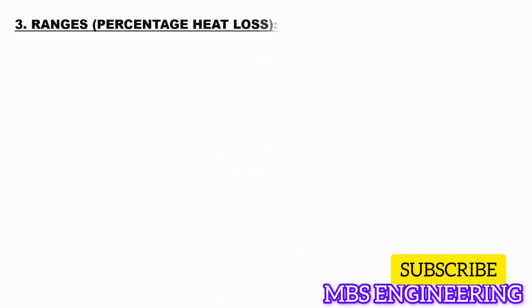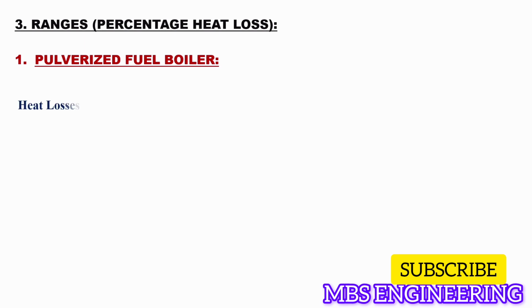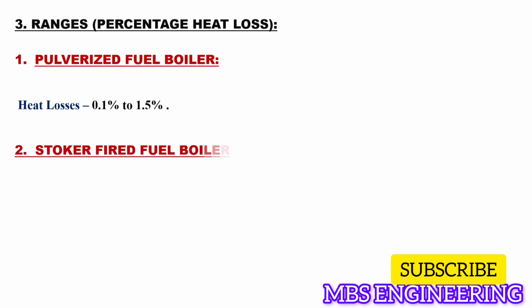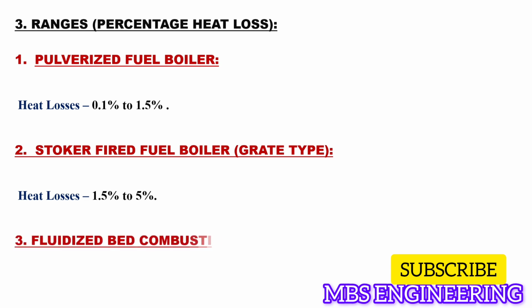Next, we will learn and understand the ranges of percentage heat loss due to unburnt carbon in bottom ash in a boiler. In pulverized fuel boiler, its percentage of the heat losses ranges from 0.1% to 1.5%. In stoker-fired fuel boiler, grate type, its percentage of the heat losses ranges from 1.5% to 5%. In fluidized bed combustion, its percentage of the heat losses ranges from 0.2% to 1%. Even small percentages can cause significant energy loss over time. These losses don't contribute to steam generation but still consume fuel energy.